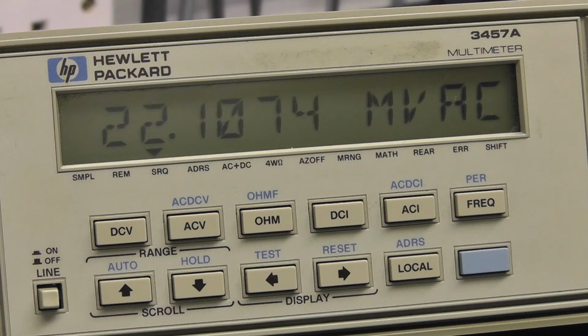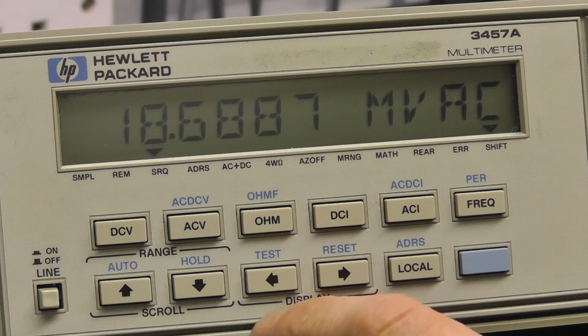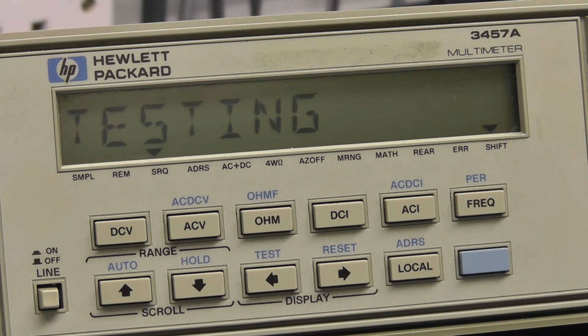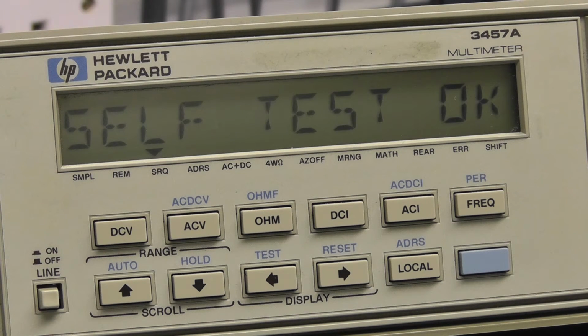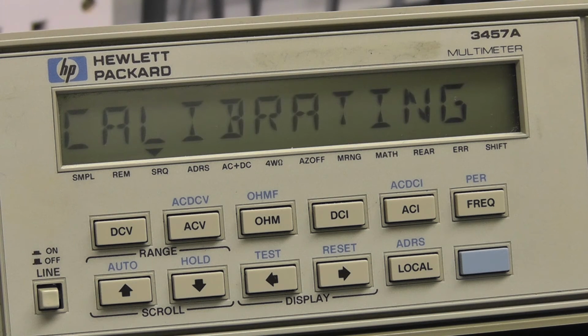So I've just come into the workshop again after dinner, and this is what happens when you do a self-test now. Self-test okay. So that's the first time we've ever had that. That's obviously cleared the problem, possibly noise being picked up in the AC board. The final and ultimate test is to do an auto calibration on it, so we're going to do that now. I'm not going to enter the digit to calibrate just the AC level. I'm going to calibrate the whole thing.